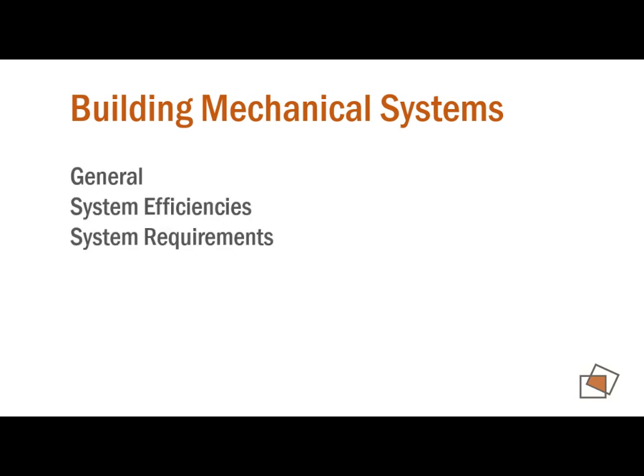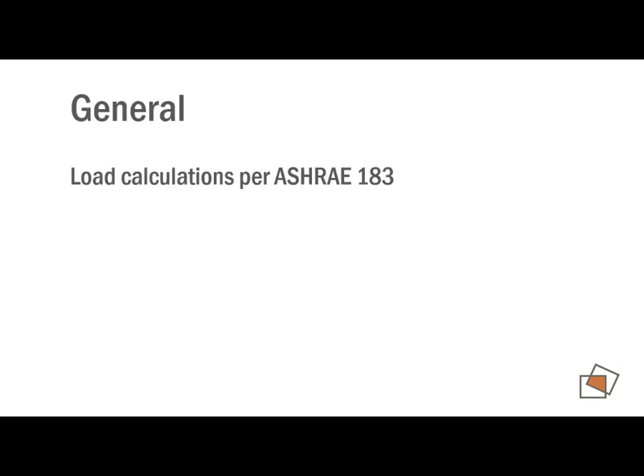So here's how I see the mechanical systems being broken up. First, there's general requirements again, then they prescribe efficiencies. They have specific requirements associated with the equipment, and then there are some requirements that you have to meet on the controls. So as far as general requirements go, they tell us how to run our load calculations. We have to run it in a method that complies with ASHRAE 183, and they don't want you to oversize the equipment. That's a big source of energy loss and can really hurt your efficiency and your performance of your systems. So swagging a safety factor on something is not acceptable according to the energy code here.